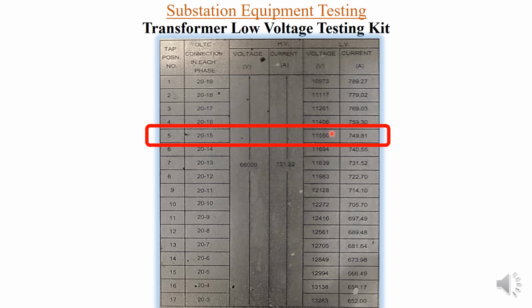There is another test called the turns ratio test. That is a higher version of the low voltage ratio test. So if you are conducting a turns ratio test, then there is no requirement to do this voltage ratio test. In the next video we will see what the turns ratio test is, how it is done, and what its importance is. So friends, I hope you have understood the voltage ratio test, and you will be able to perform it on transformers whenever you require.